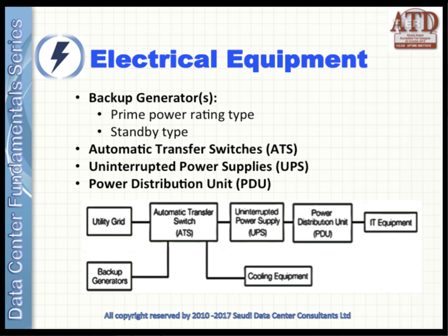Electrical equipment covers all power-related devices. First, the backup generator — which can be prime power providing an unlimited number of hours, or the standby type which has a limitation on hours throughout the year. Second, the ATS, used to transfer the load in case of city power failure. Third, the UPS, used to feed the data center with power when city power goes out. Finally, PDUs, which supply power to IT equipment.